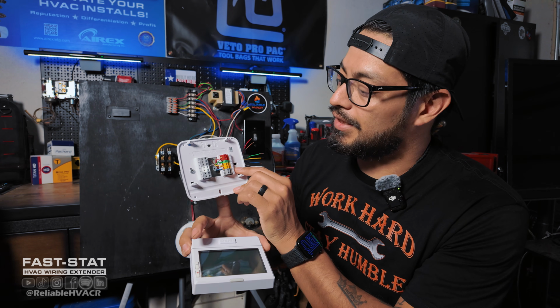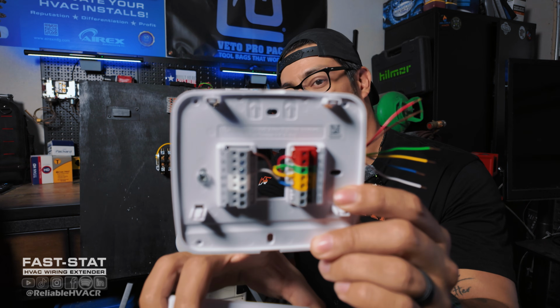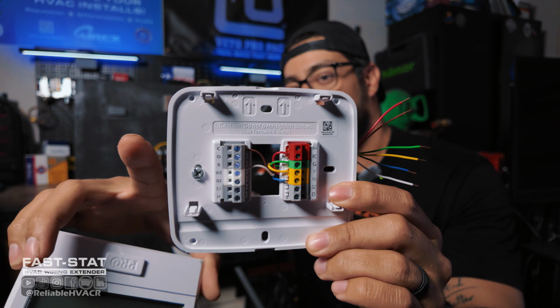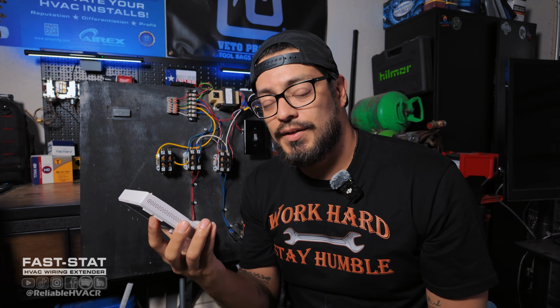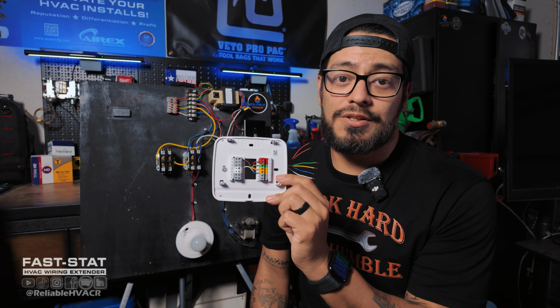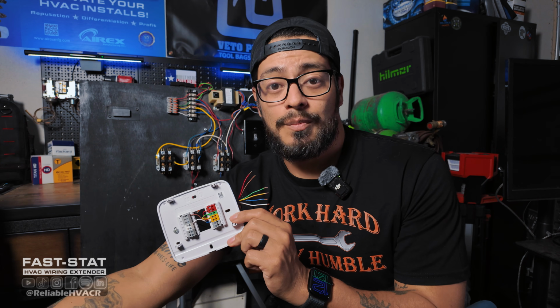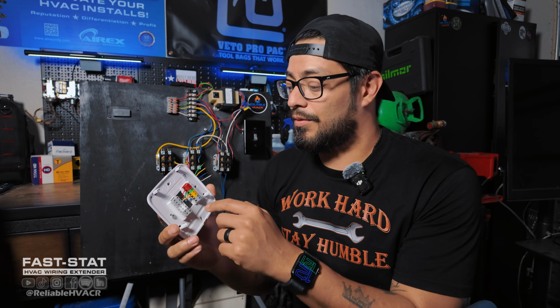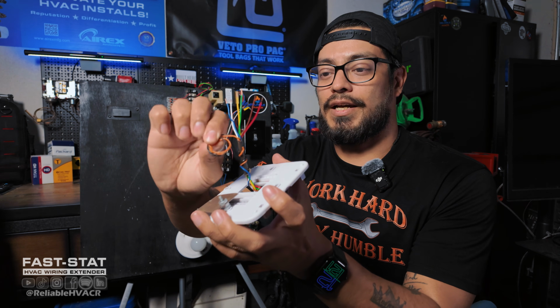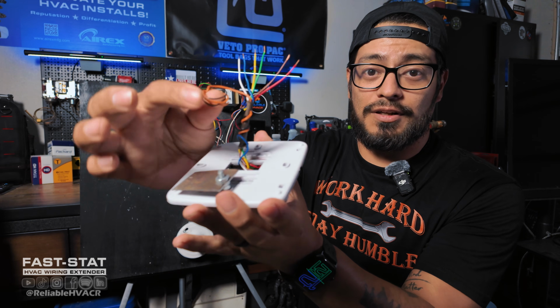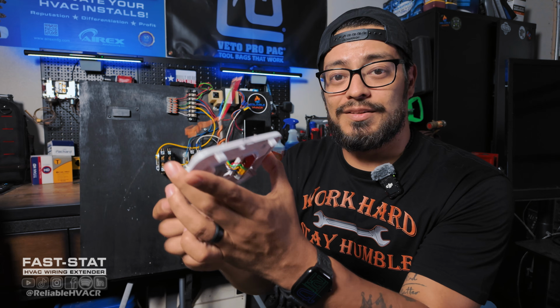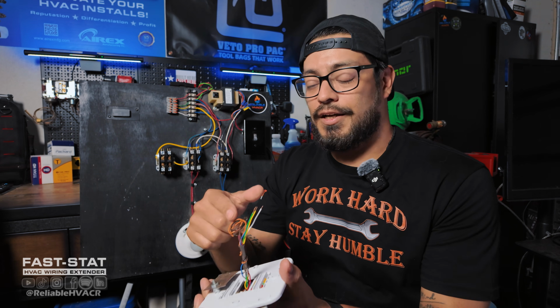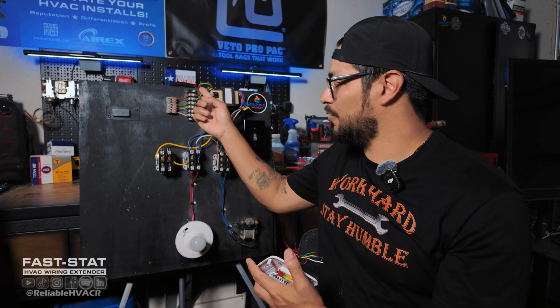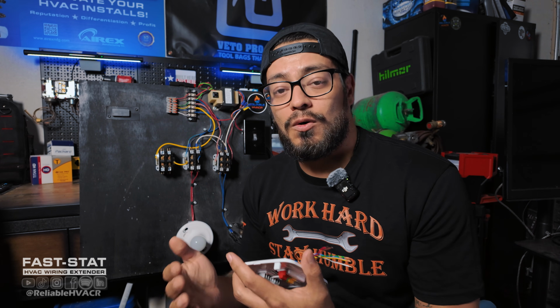The next thing you're going to look for is, do we have a common hooked up? On this one, it is on the top right. If there is nothing there and there's batteries, more than likely your batteries are dead, you put them in. But you can also try to, I wouldn't say upsell, but recommend that we run a common. Now, you need to look here at the thermostat wire in the wall. And if you're lucky and you have extra wiring, you can just connect one to your common here. And then the other end of that would be in the indoor coil, indoor furnace, or on an RTU, it would just be wherever your transformer is, this terminal board right here. And then just ground it out or run it to a common.